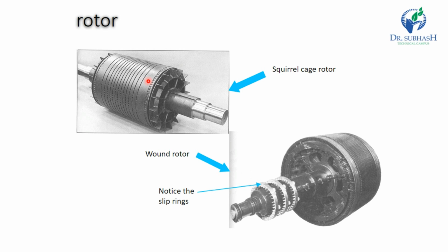Generally, the rotor bars are skewed by an angle just sufficient to cause induction of two equal and opposite harmonic EMFs in each bar. Thus, the bars must be skewed such that they lie under alternate harmonic poles of the same polarity, so that they are skewed through two pole pitches.